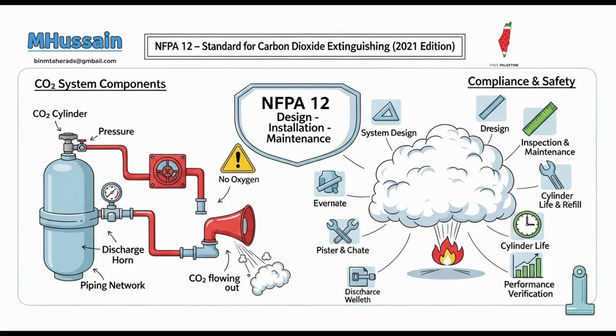That sounds like a powerful one-two punch. What are some of the other significant advantages, the pros, of using CO2 systems? Why choose CO2 over other agents? Well, the benefits are indeed substantial for specific applications. Firstly, it's non-corrosive and non-damaging to most materials, leaving absolutely no residue behind. We mentioned the no cleanup. That's huge for electronics. It's a massive advantage in environments with sensitive equipment like electronics, machinery, or priceless artifacts. Imagine a fire in a data center. Using water would be disastrous. Loss. Right. But CO2 cleans up, or rather disappears without a trace, drastically reducing downtime and cleanup costs.